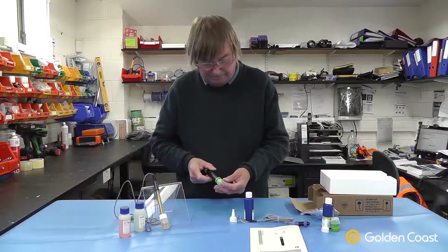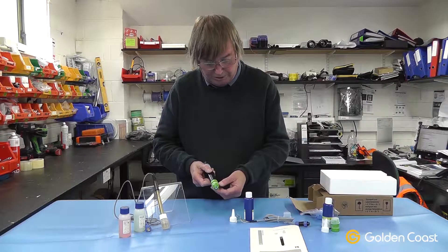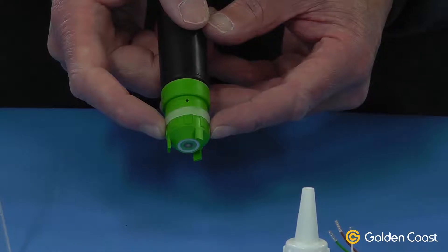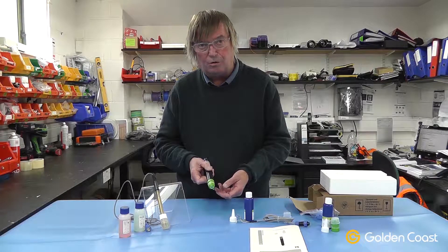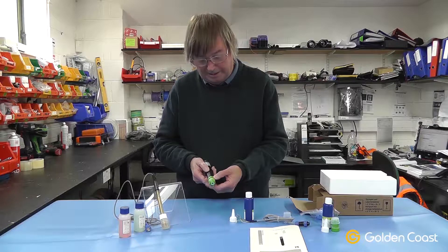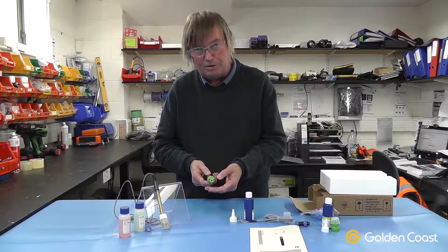The amperometric probe itself comes with a protective cap on the end and a silicon band around the outside, which we've already pulled down — it exposes a little weep hole in the side of the cap. This must be removed before you do anything with the cap, either taking it on or off. This relieves the pressure inside the end cap; if you don't have that hole exposed you'll blow a hole in the little membrane at the end, and that's damaged forever.